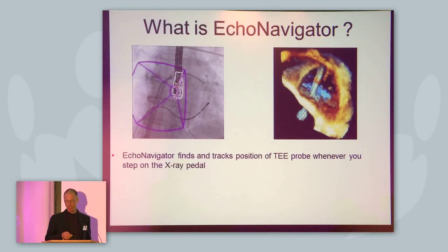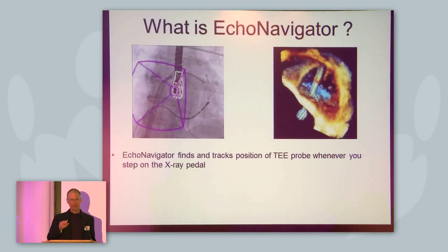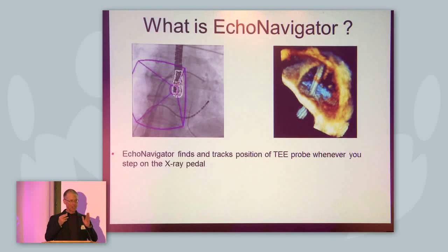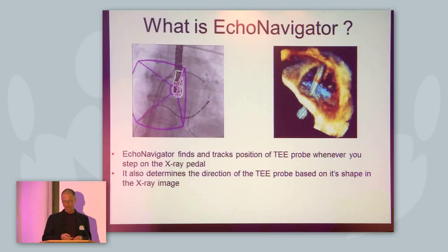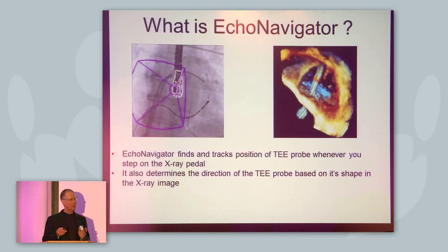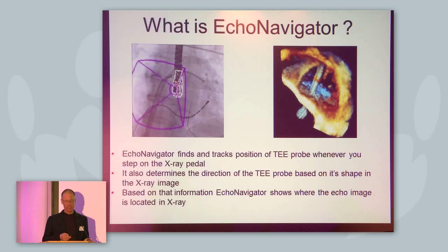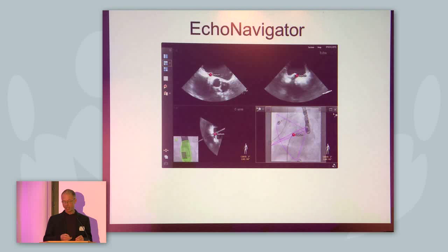So what is the echo navigator? It basically finds the position of the TEE probe on fluoro and recognizes where the TEE probe is whenever you step on the pedal. It also determines the direction of the TEE probe on fluoro, so it can correlate the images obtained by fluoro and echo. Based on that information, the echo navigator shows where the echo image is located in x-ray.